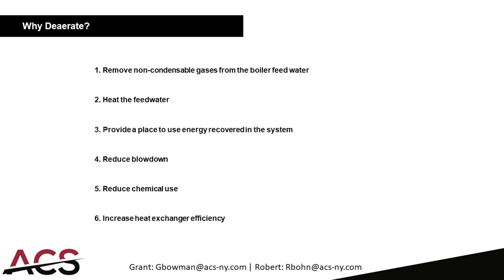Why use a deaerator? It removes non-condensable gases from the boiler feed water — primarily oxygen. It heats the feed water, helping efficiency and reducing thermal stresses on the boiler, avoiding the shock of super cold water heating up quickly inside. It provides a place to use energy recovered in the system, reduces blowdown, and reduces the chemical usage needed to treat the water. It also increases heat exchanger efficiency — your boiler. Additionally, cold feed water going into a boiler can cause condensation, which is basically an accumulation of acids that could corrode the boiler, so by preheating the feed water you eliminate that possibility.